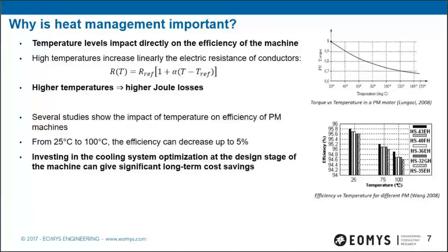Heat management is also very important for efficiency. Joule losses, due to electric current in conductors, are directly related to the electric resistance of the material, and resistance increases with temperature — so higher temperatures mean higher losses. For PM machines, studies show that increasing temperature can decrease efficiency by up to 5%. Investing in cooling system optimization at the design stage can give significant long-term cost savings.